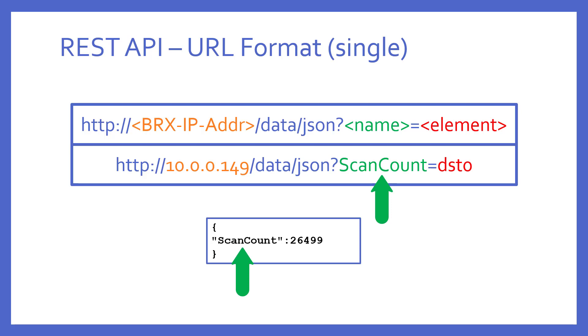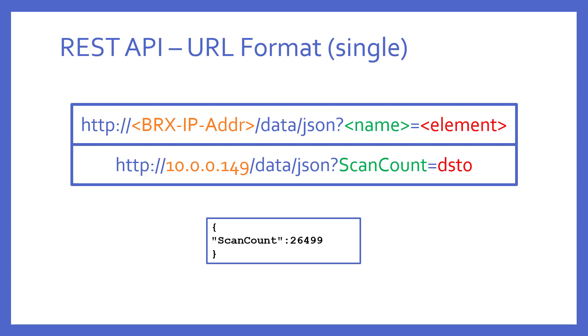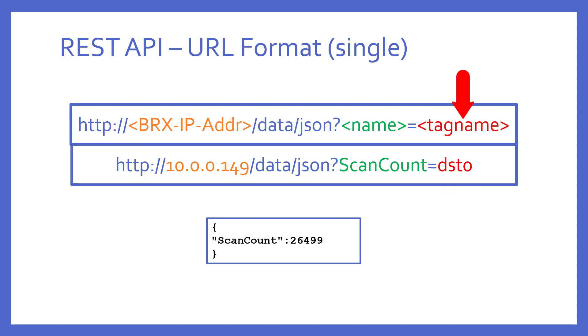Also, even though this value is constantly changing, this URL will only give the value of DST that was read at that moment. It will not continually update unless you keep hitting the refresh button in your browser. Another very important thing to know here is that I don't have to use the raw element name like DST0. Instead, I could use the tag name. This is also called a nickname in Do More Designer. That is either automatically assigned in the case of system elements or one that you have previously assigned in your BRX PLC.